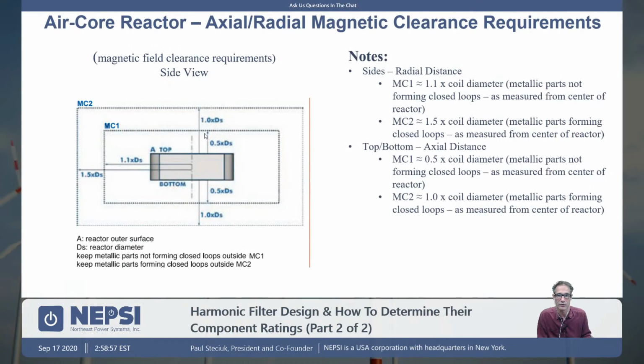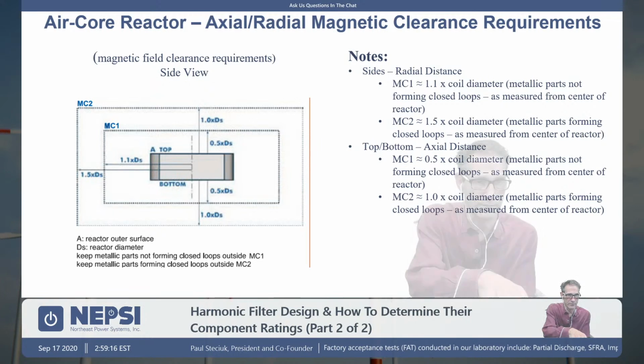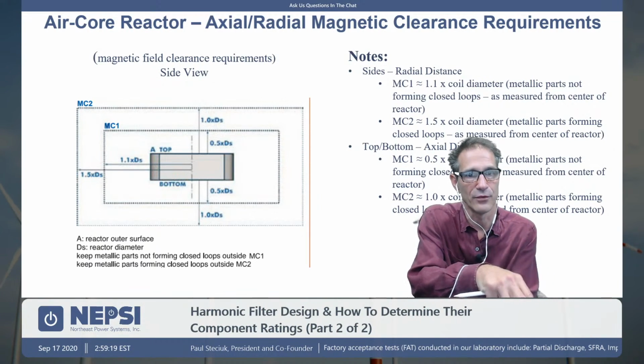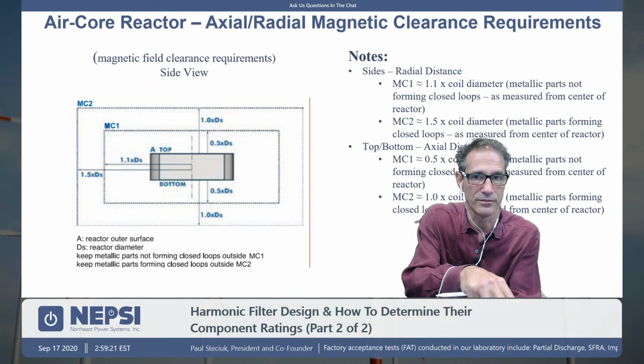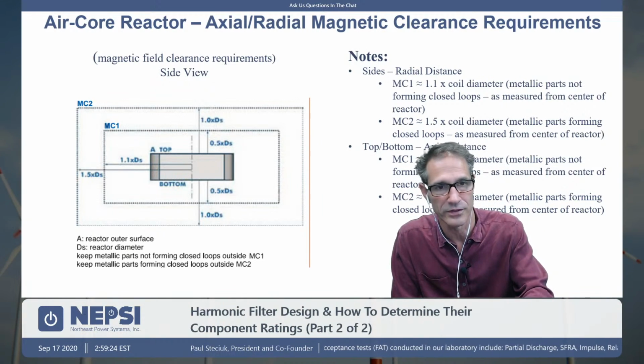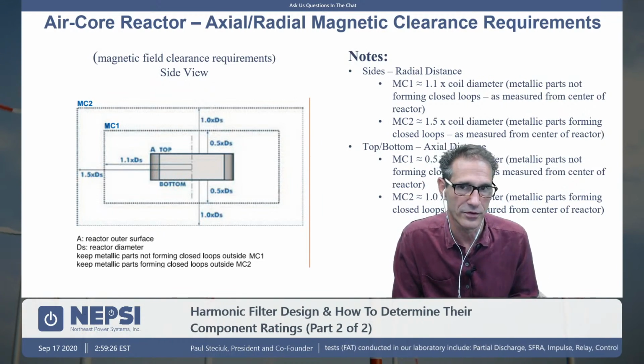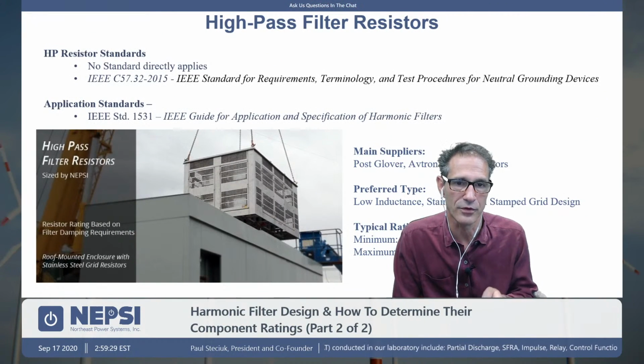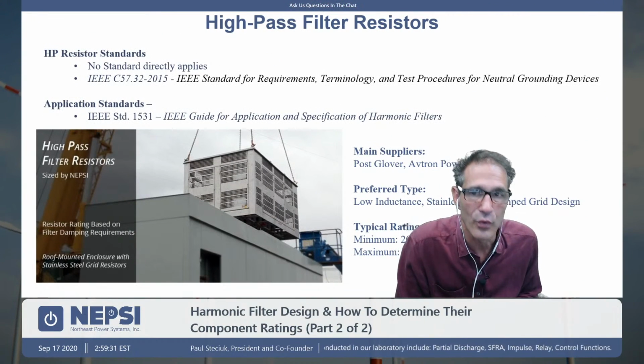It's really why the metal enclosed solutions are sometimes just 20% of the area requirement of an open air solution. It's because we don't have that magnetic field clearance issue that air core reactors have. You also have clearance issues in the axial direction, and that's what this is showing, that if you mount the reactors at ground potential, you got rebar in the ground, that rebar can heat up. So you have to be concerned about the heating effect of what's in the concrete underneath the air core reactor. So we're going to kind of burn through this pretty quick.